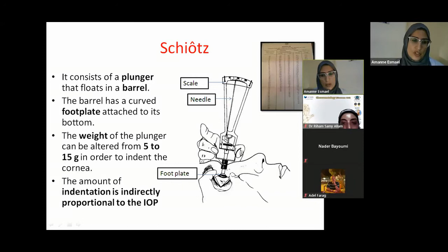So how do we perform it? First, we have to calibrate the device, and there is a little metal block present in the box that you can use for calibration. Then sterilize the device and instill topical anesthesia. The patient should lie on their back, and you instruct them to look straight ahead to avoid accommodation. Then you hold the instrument perpendicular to the corneal surface. You get a number on the scale, and you move on to a conversion table and see what intraocular pressure is written opposite to that number.